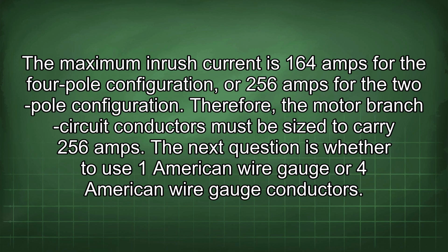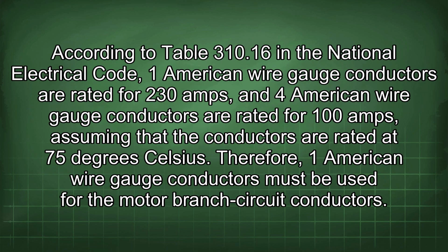The next question is whether to use 1 American wire gauge or 4 American wire gauge conductors. According to Table 310.16 in the National Electrical Code, 1 American wire gauge conductors are rated for 230 amps, and 4 American wire gauge conductors are rated for 100 amps, assuming that the conductors are rated at 75 degrees Celsius. Therefore, 1 American wire gauge conductors must be used for the motor branch circuit conductors.